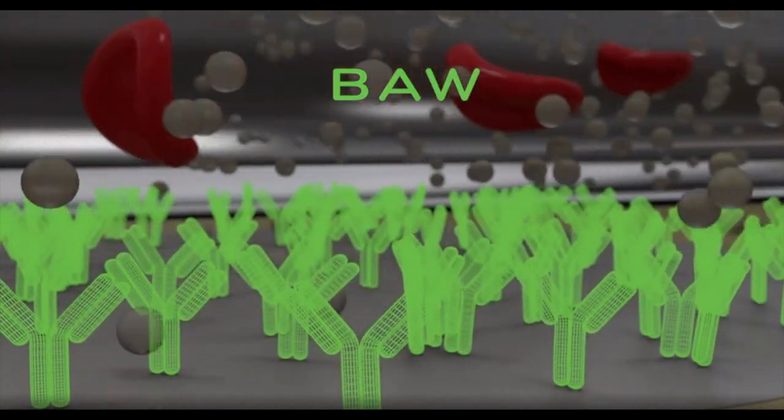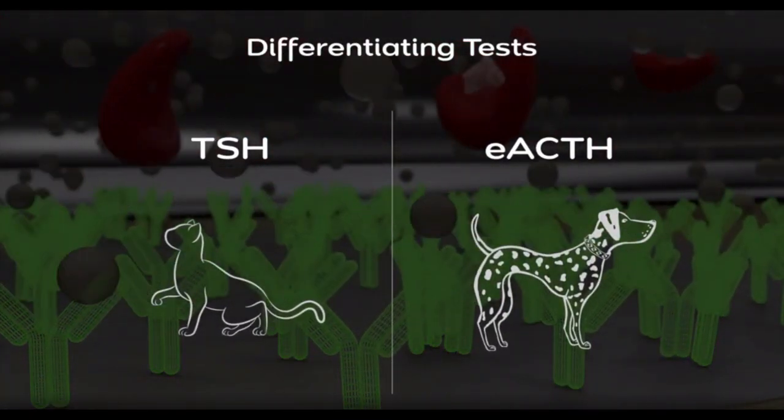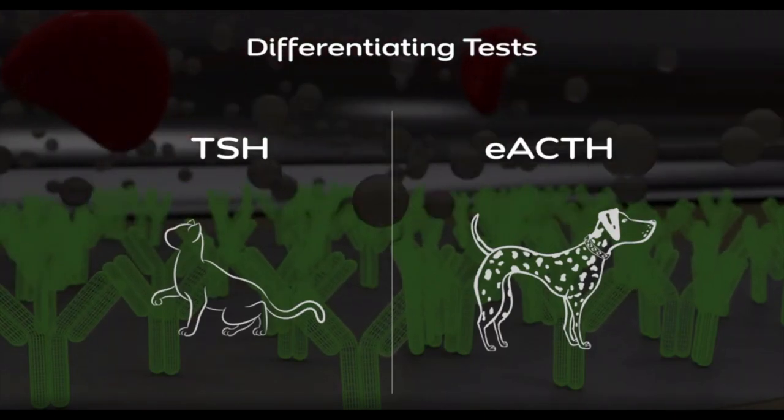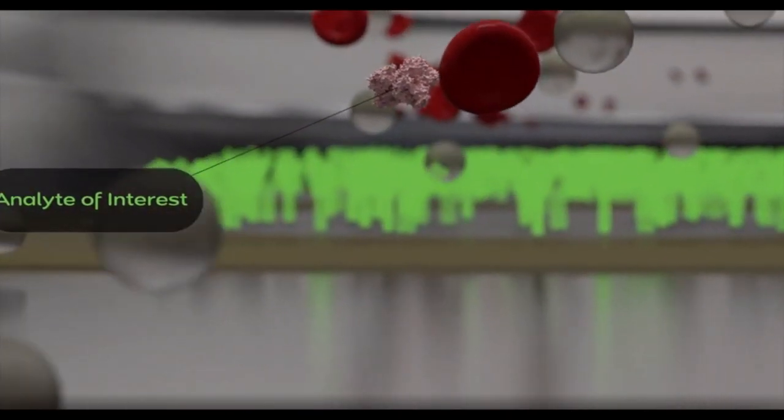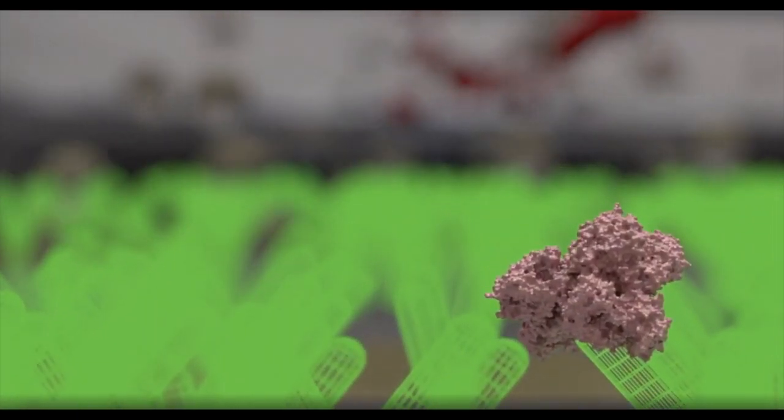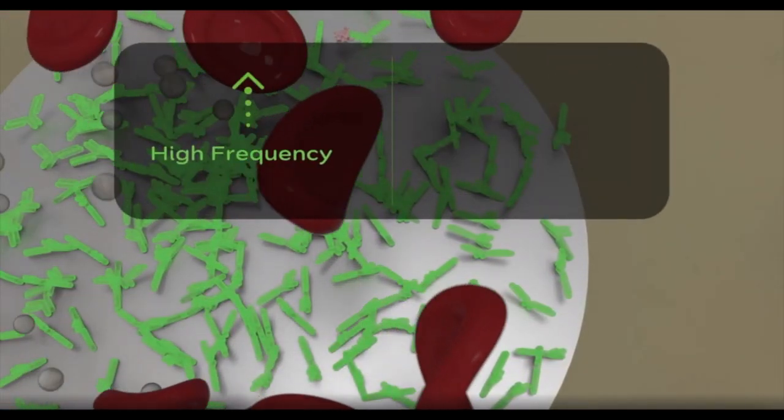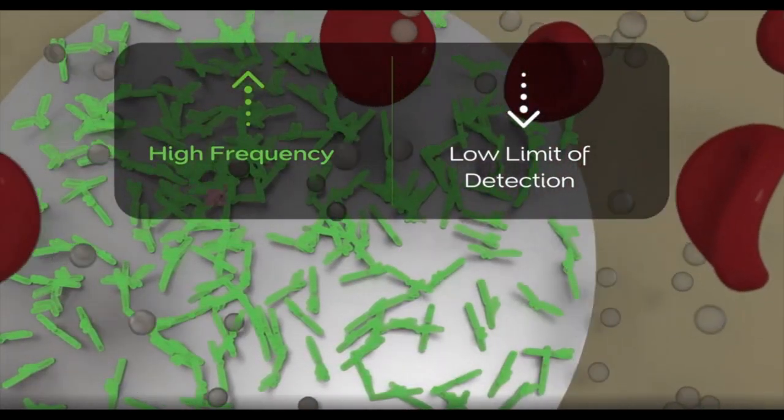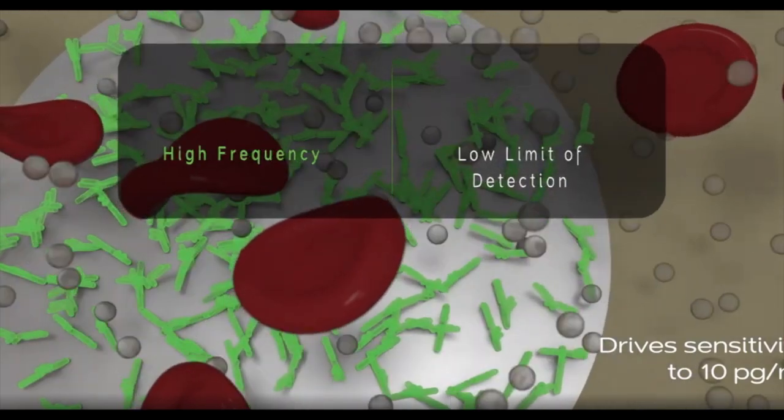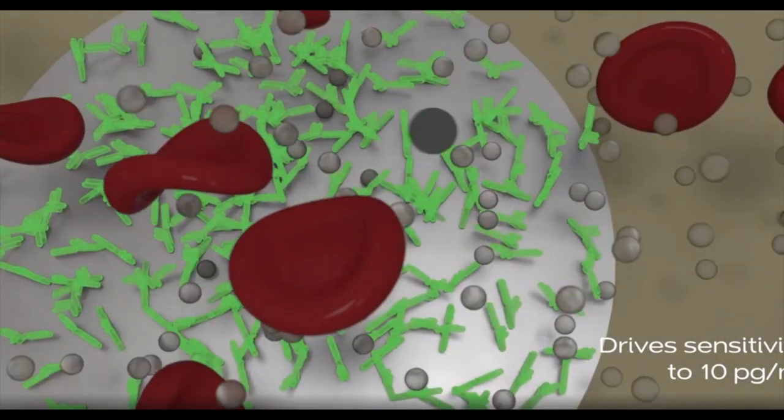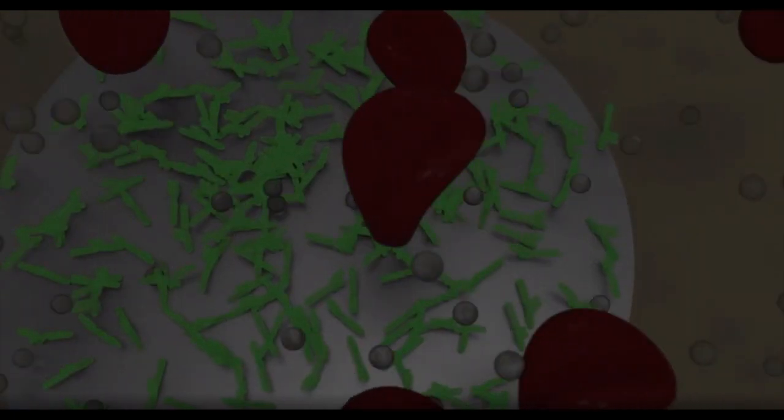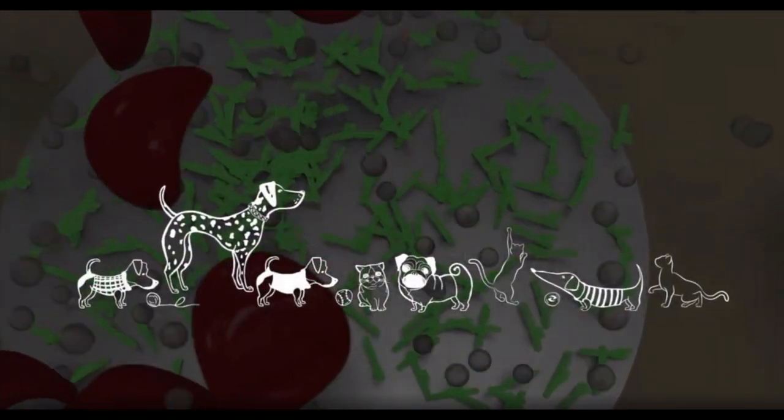Trueforma uses a completely different, new, and extremely sensitive method of detection based on bulk acoustic wave or BAW sensor technology. The BAW sensor can detect subtle changes in the mass of specific molecules associated with a particular test. When an analyte of interest passes through the fluidic channel, it binds to the target molecule, forming a slightly heavier particle that resonates at a different frequency. This change can then be converted to a known concentration. Because BAW operates at high frequencies, it has a very low limit of detection, allowing these changes to be measured down to a level of 10 picograms per milliliter.